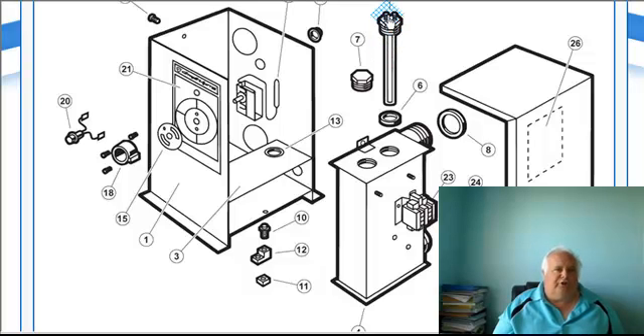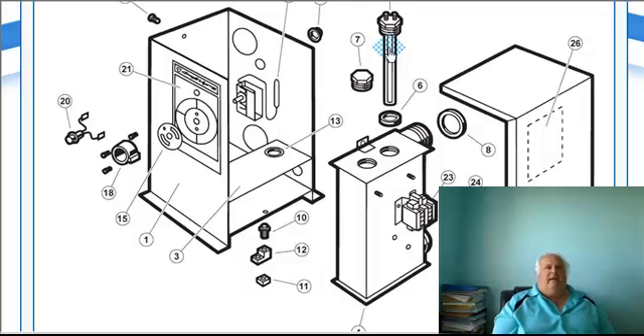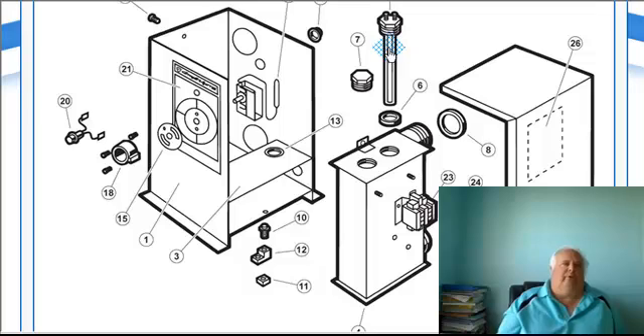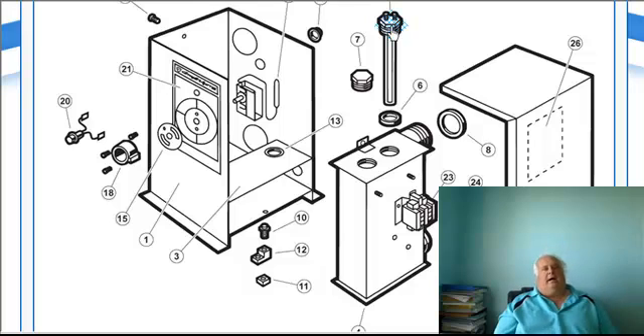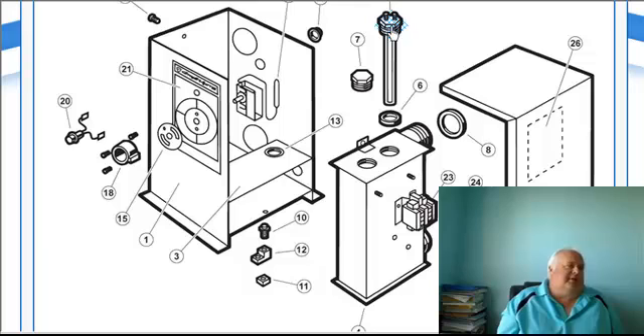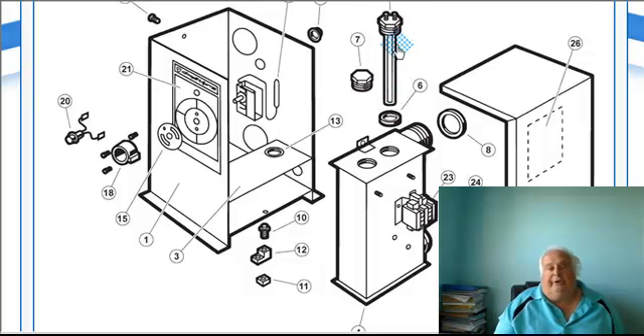Now you could have voltage here at your heater, but it's still not heating. That's why I say to have an amp probe. If you are running amperage, you're physically reading amperage, you're creating heat. But if you're just checking for voltage here, you could have voltage but a bad heating element. So therefore, she isn't going to heat. So if you got voltage up to here, and you got 208 volts or 220 volts, take the wires off. You can ohm them out. The reason why I like checking amperage is when I was out in the field, it's not often, but I ohmed out a couple of bad heating elements that ohmed out good, but they read no amperage. That's why I always tell you to make sure you have an amp probe.